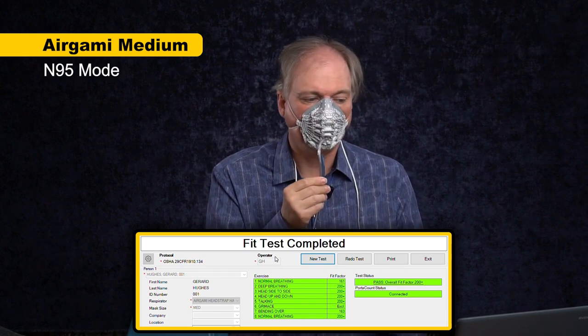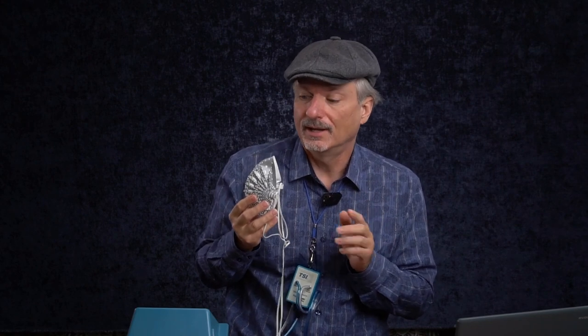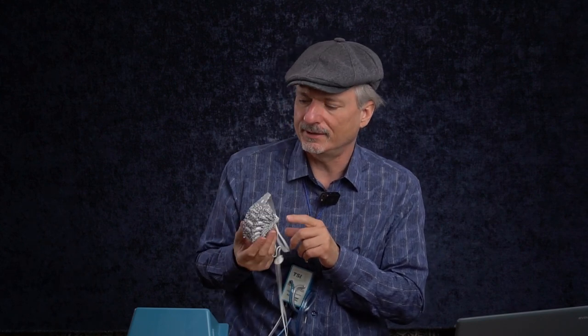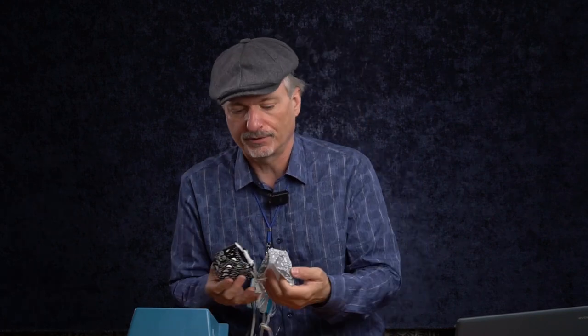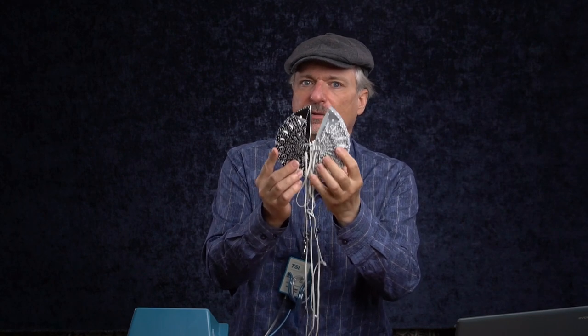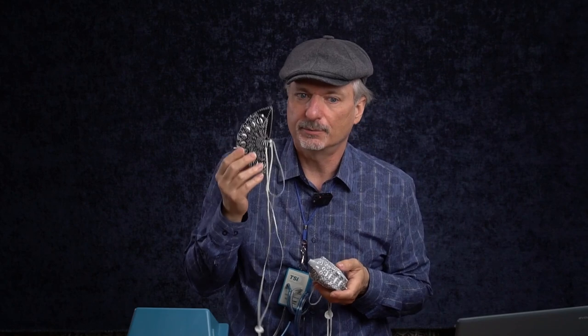Overall pass with a fit factor of over 200. After doing the test I have to say I'm impressed. I wasn't sure what to expect, but the Airgami passed on me in the medium size in every single exercise — and that doesn't always happen. What impressed me is that I didn't know if these flat folds could create a seal against your skin. I did crank these straps up pretty tight to give this a fair shake. To compare, I'm going to do an N95 mode test of the large size — just a single static fit test — to see if that larger size and nose bridge distance makes a difference.